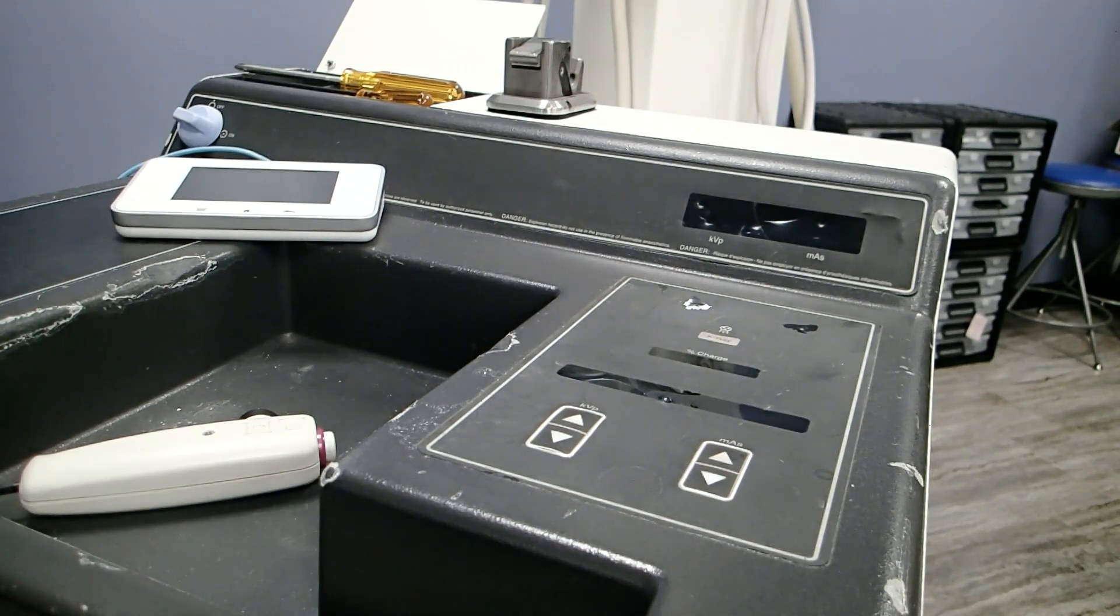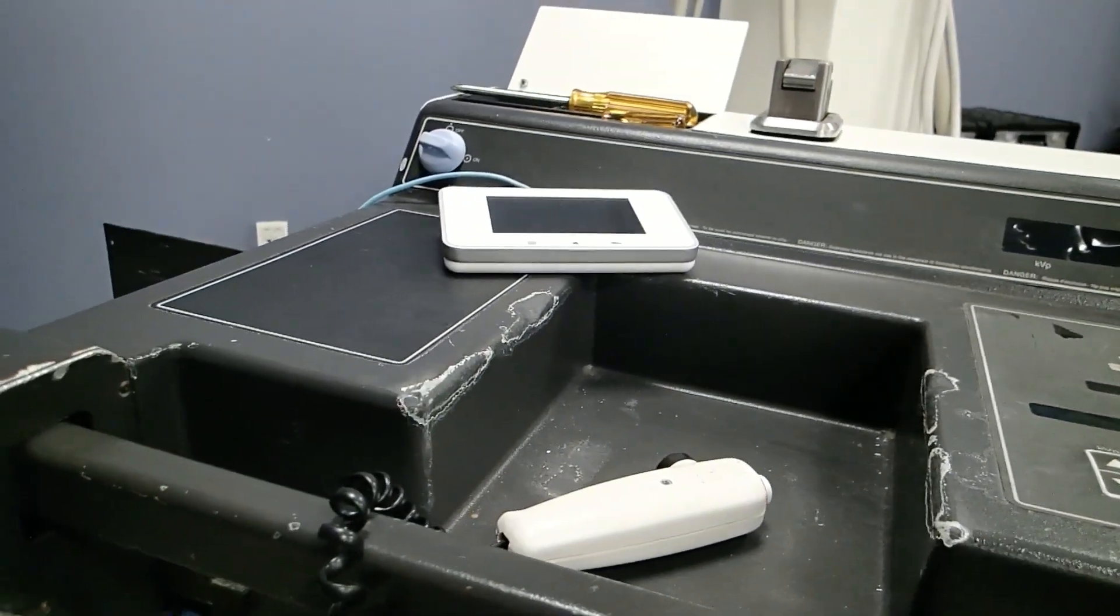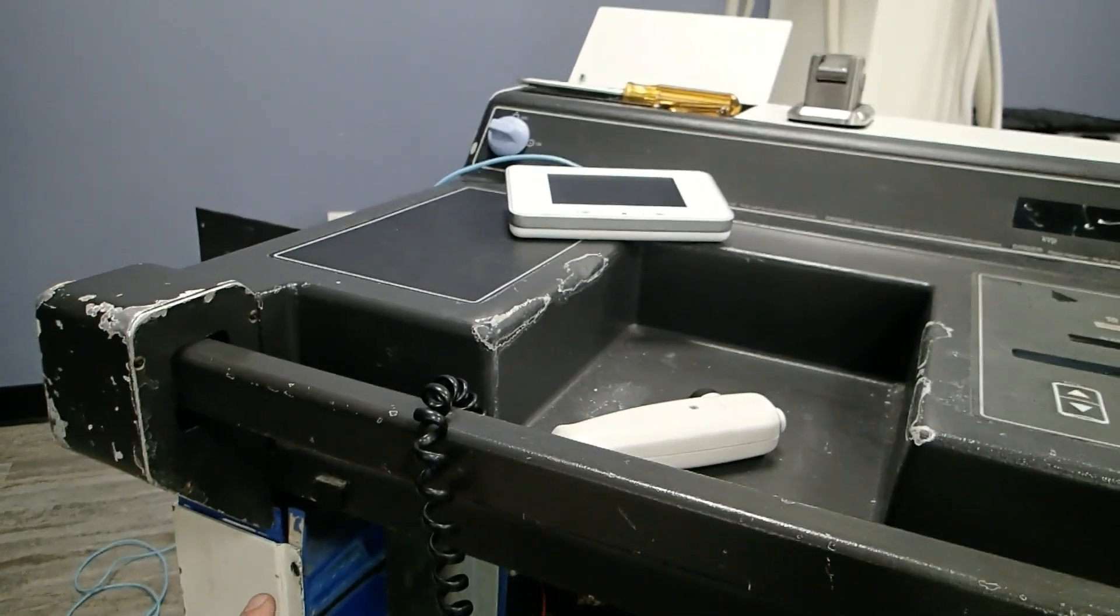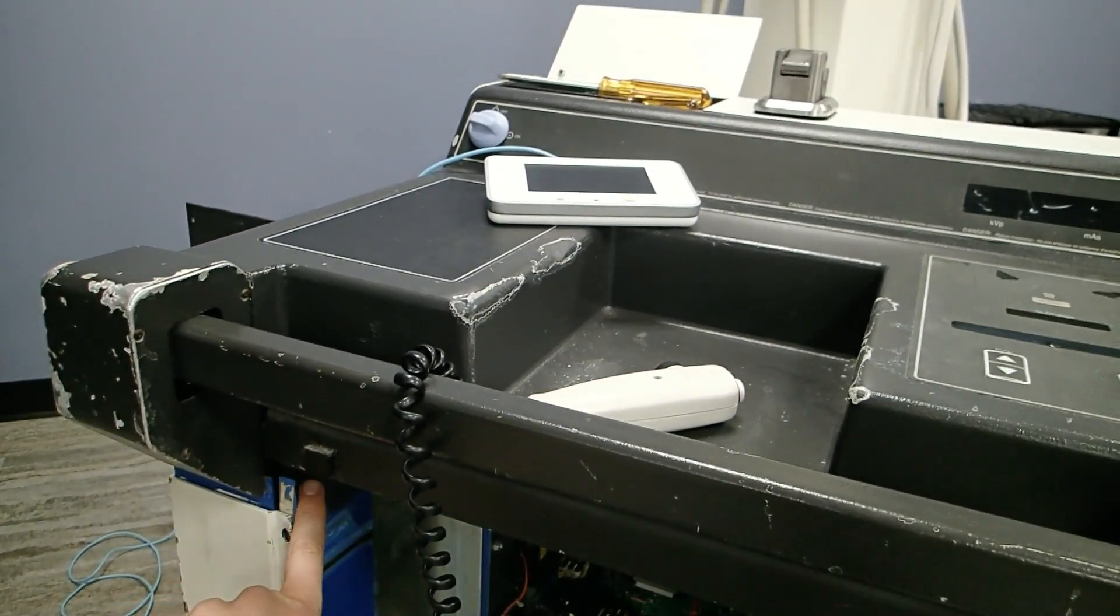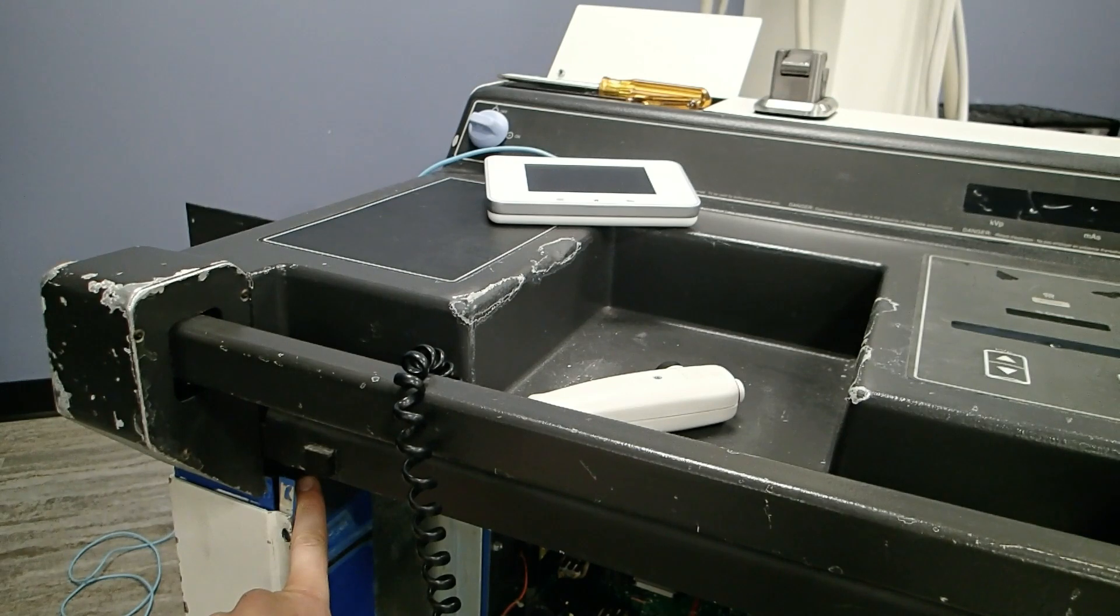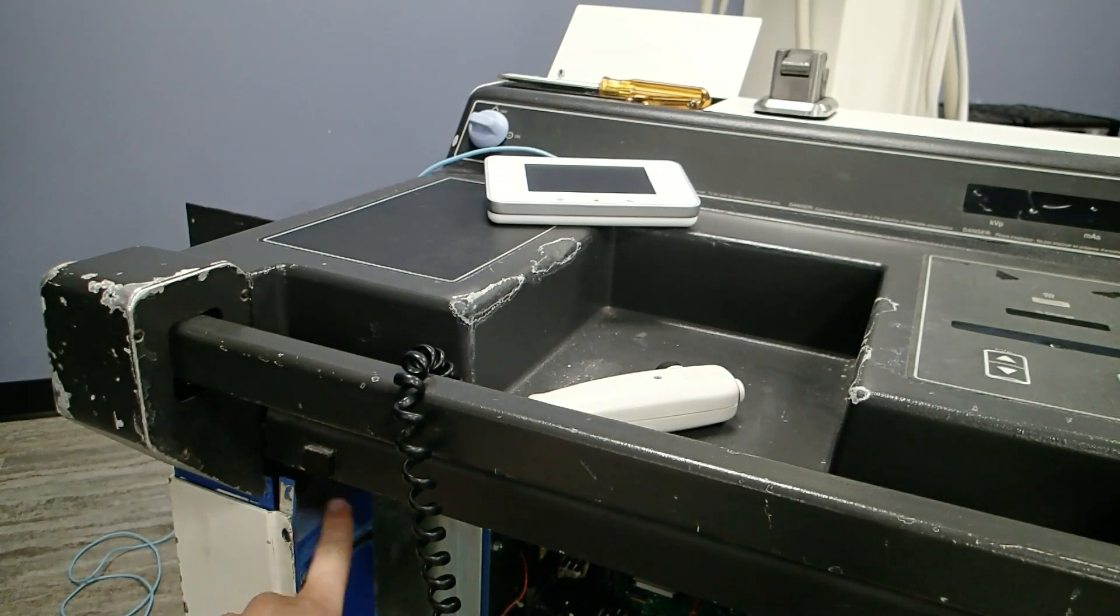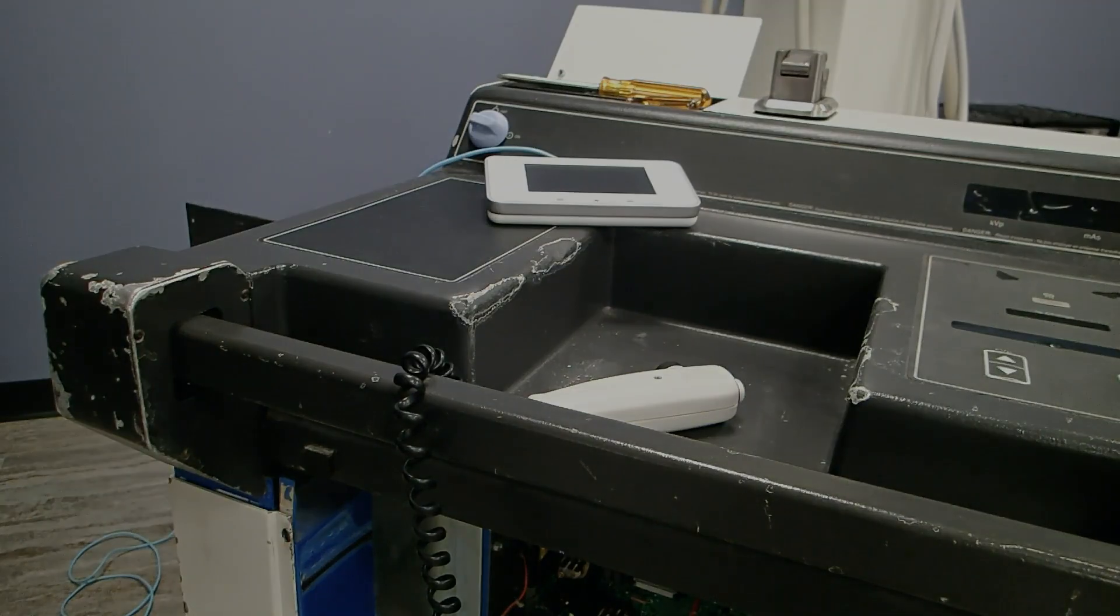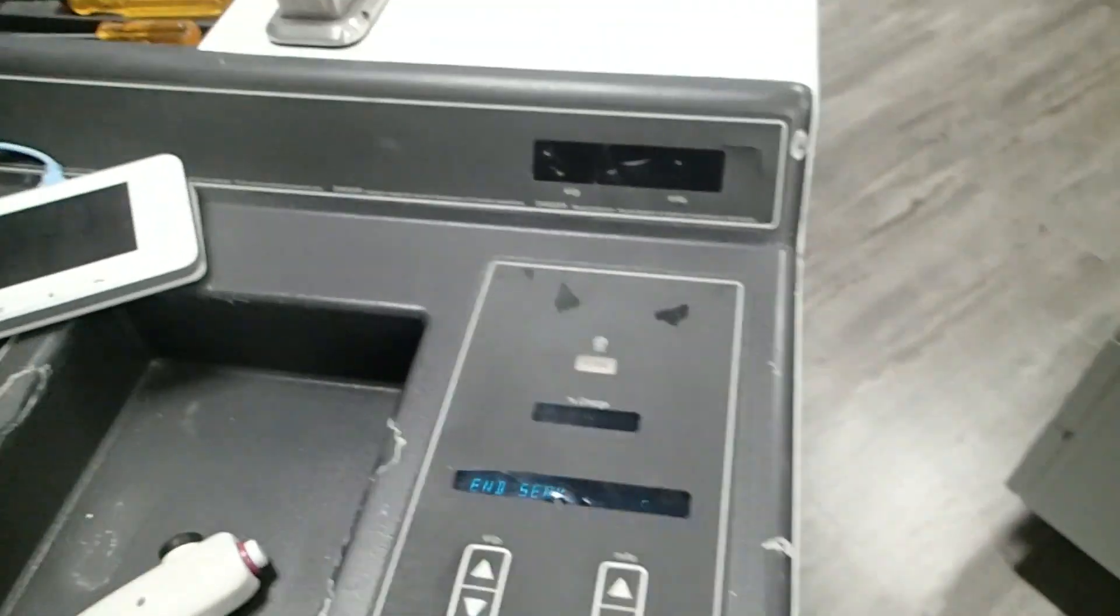We need to make sure we're in service mode. Right now we are in service mode, but if you're not familiar with how to get to service mode, there is a switch right in here that needs to be flipped on. When that's flipped on and you turn the power on, it will enter service mode.